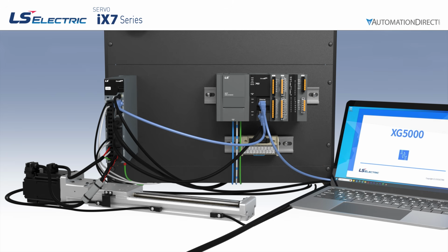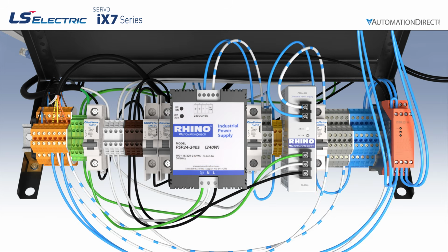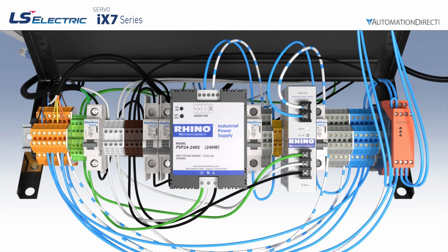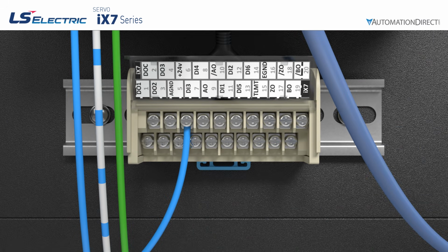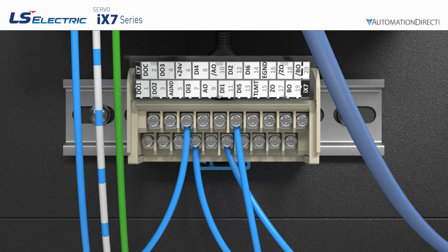Now it's time to wire our I/O. For the drive, we're using 3-wire NPN-style home and overtravel sensors. Using terminal blocks allows us to avoid stripping back the sensor jacket. We'll supply 24-volt DC to each sensor's positive wire and 24-volt common to each sensor's common wire. We'll also bring 24-volt DC from the I/O supply to the drive's plus 24-volt terminal. We can then land the output wire of each sensor to the digital input terminal on the drive. DI1 is our positive overtravel, DI2 is our negative overtravel, and DI3 is our home sensor.